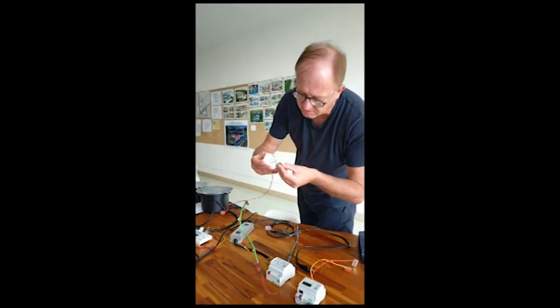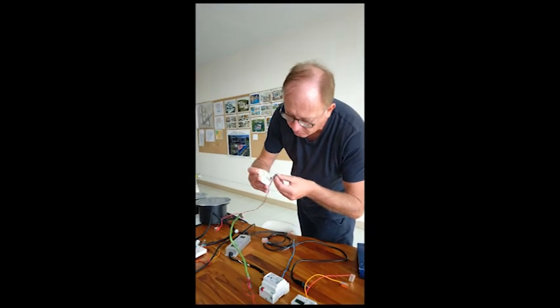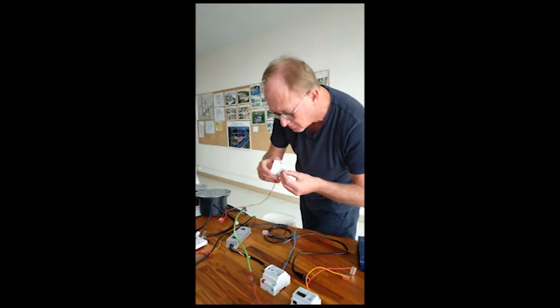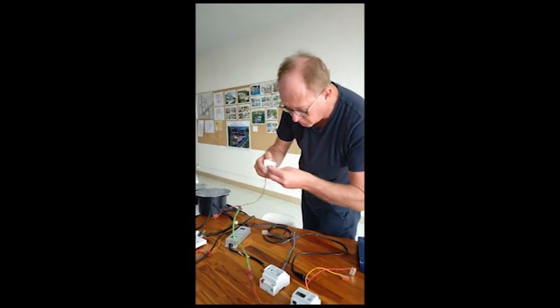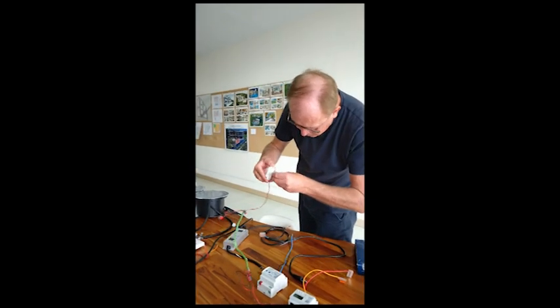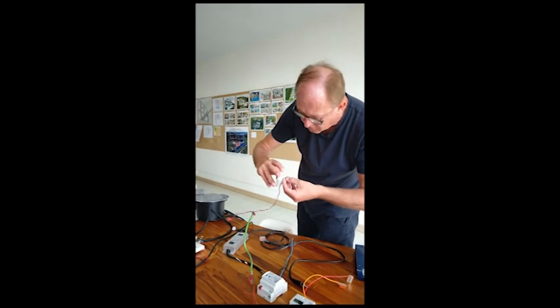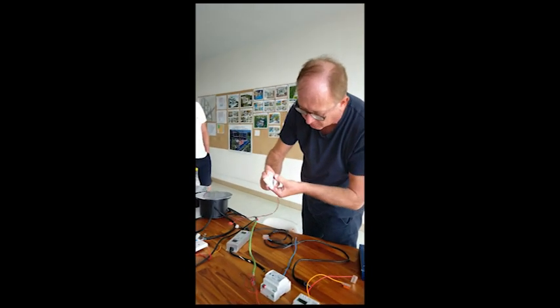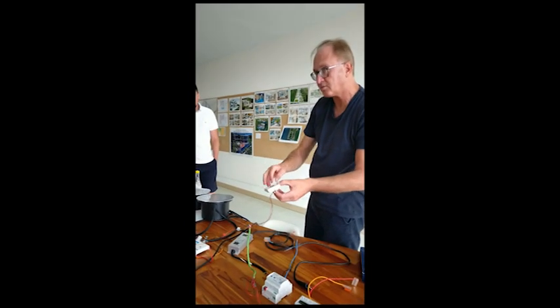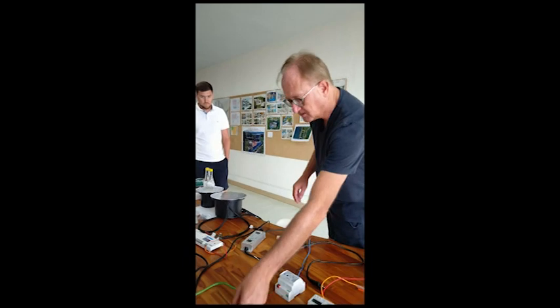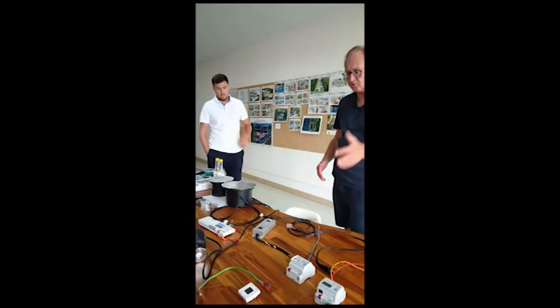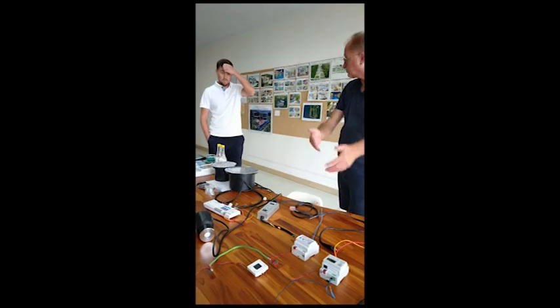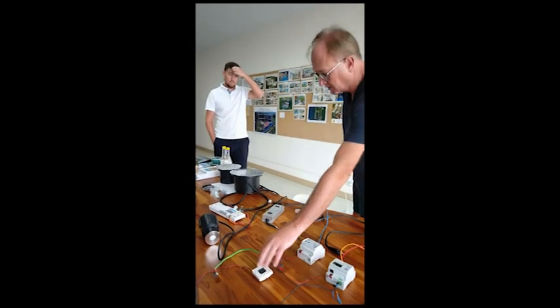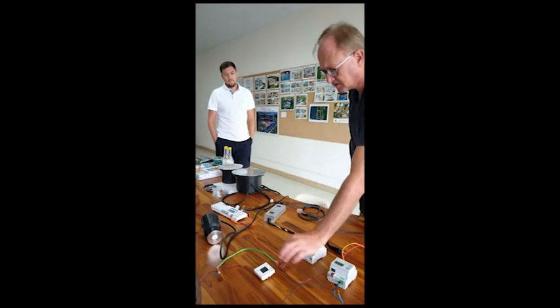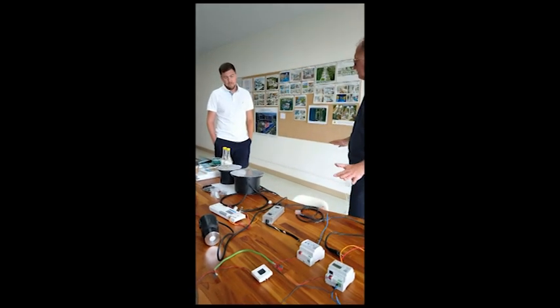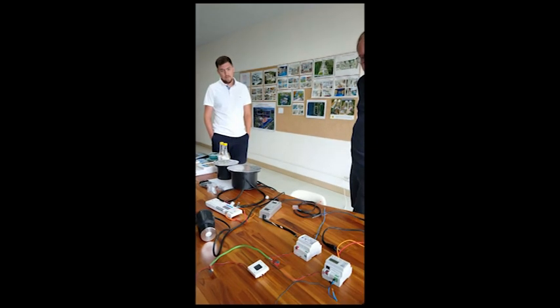So where's the correct way? Is it like that? No, the other way around, so this way. Put it in, and this device is obviously already programmed. Once it gets the bus power, 24 to 30 volt, it works and does what it's programmed for. But you can take it off and put it on any other node - all KNX nodes are equal. You just need power.